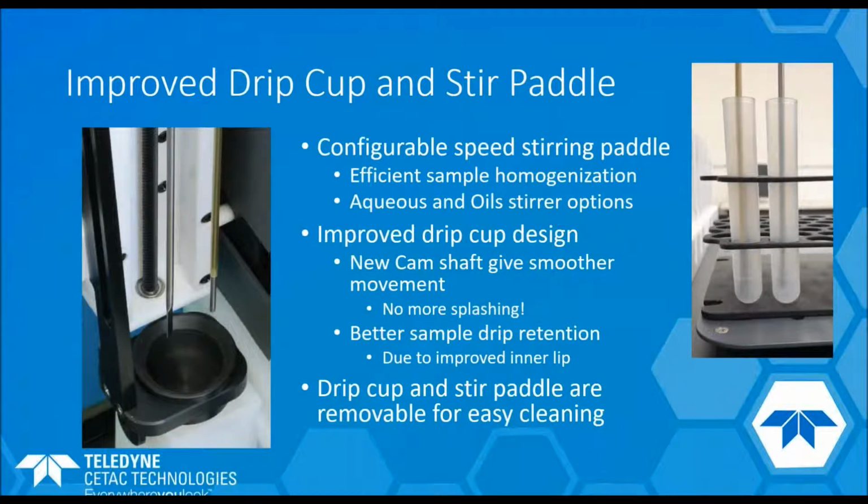In addition to the probe, there's its buddy, the stir paddle. So we still have the dual Z drive on the 7400 like we did on the 1400. And you can see on the right, I've got a picture of your probe and your stir going into two tubes side by side. That stir spins to prepare the next sample as the first sample is pulled up.